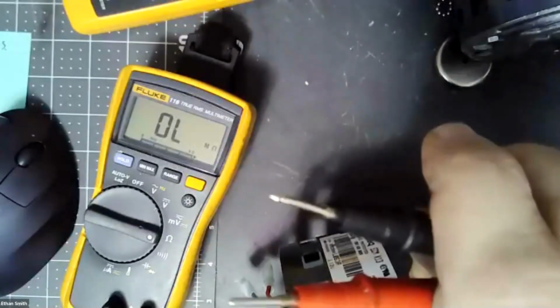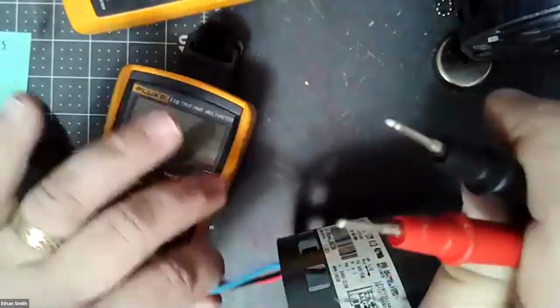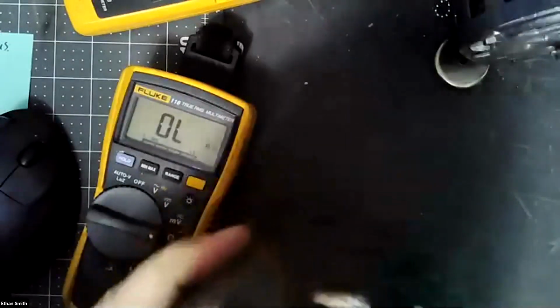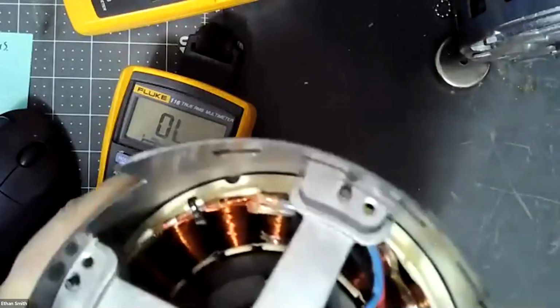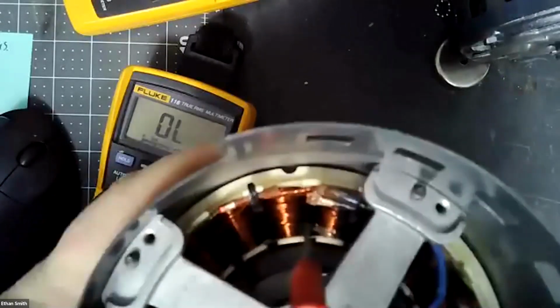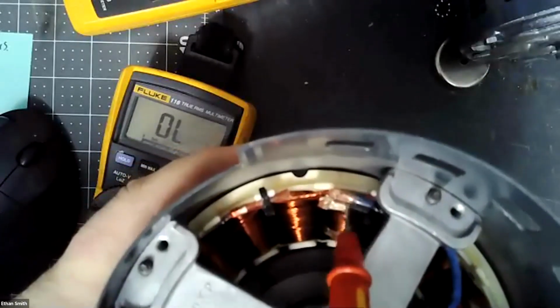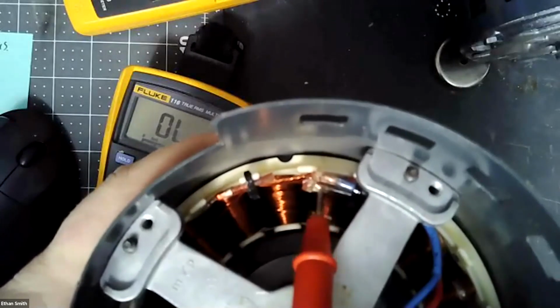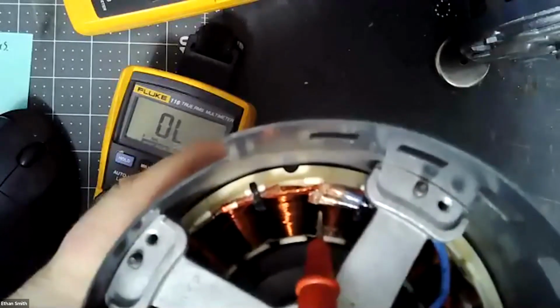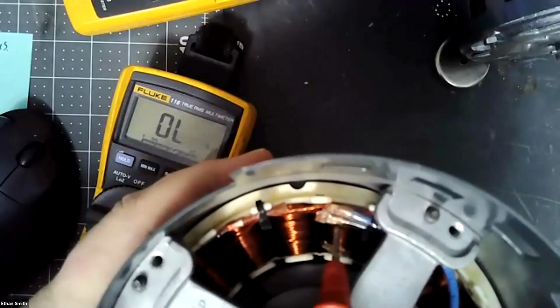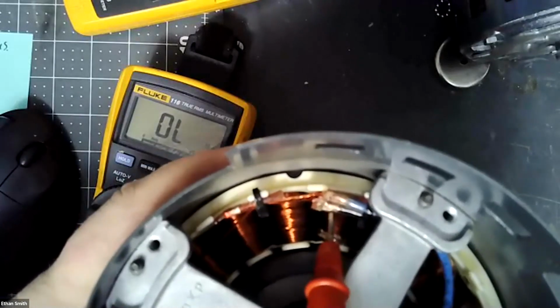Yeah. So you can have loose connections inside the motor. If you look down inside this motor, see if I can get an angle on it here. Right down here is where those connections will fail. A little tough to see, but there's a little staked on connector right there at the tip of my probe where those wires come in. And they're tied to the motor. That's where motor connections fail. So that can get loose.